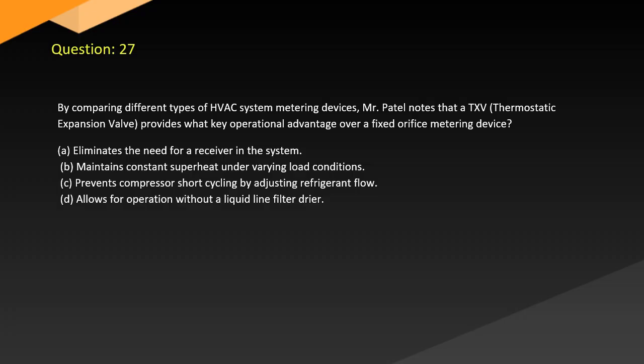Question 27. By comparing different types of HVAC system metering devices, Mr. Patel notes that a thermostatic expansion valve provides what key operational advantage over a fixed orifice metering device? A. Eliminates the need for a receiver in the system. B. Maintains constant superheat under varying load conditions. C. Prevents compressor short cycling by adjusting refrigerant flow. D. Allows for operation without a liquid line filter dryer.